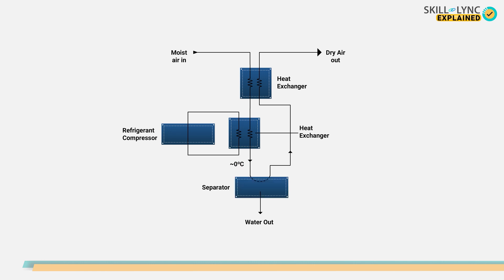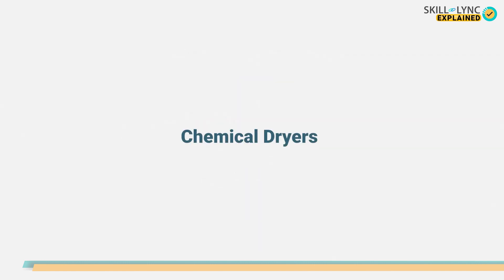To increase the efficiency of these systems, the cool air leaving the system can be used in a heat exchanger to cool the incoming air. Thus, the pre-cooled air condenses more easily, increasing the overall efficiency. But some systems require absolutely dry air, which can be obtained by using chemical dryers.